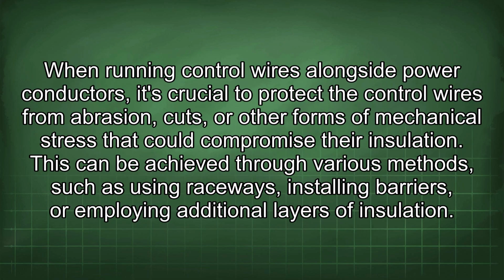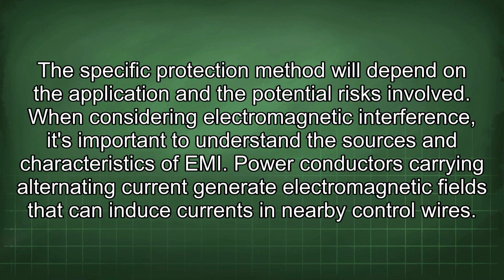When running control wires alongside power conductors, it's crucial to protect the control wires from abrasion, cuts, or other forms of mechanical stress that could compromise their insulation. This can be achieved through various methods such as using raceways, installing barriers, or employing additional layers of insulation. The specific protection method will depend on the application and the potential risks involved.